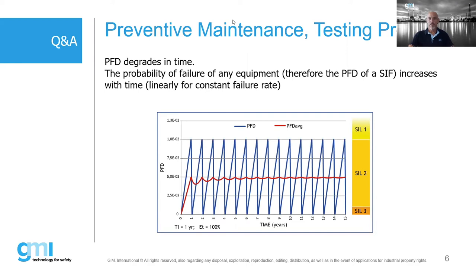So every ESD system may require a redundant power supply. That's true. Of course, the ESD system is very, very critical. Emergency shutdown systems require, of course, safety power supplies. So another question is, which is better, a non-SIL redundant power supply or a non-redundant SIL power supply? Please compare reliability and cost. Massimo, can you tell this attendee something about that? So, say we have two redundant non-SIL power supplies. Is it better to have that, or just one SIL power supply?